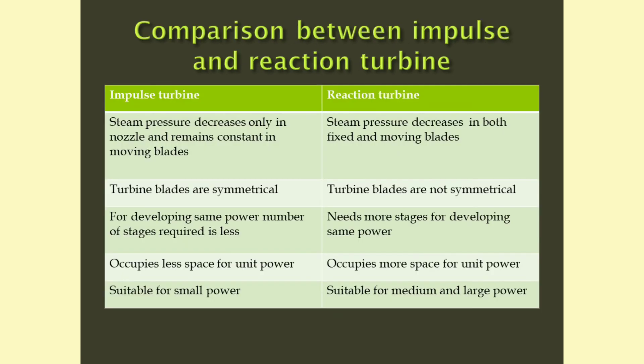We can now compare impulse and reaction turbines. For impulse turbine, steam pressure decreases only in the nozzle and remains constant in moving blades; for reaction turbine, steam pressure decreases both in fixed and moving blades. The turbine blades are symmetrical for impulse turbine and not symmetrical for reaction turbine. For developing the same power, reaction turbine needs more number of stages compared to impulse turbine, and therefore needs more space for unit power, while impulse turbine needs less space. Impulse turbine is suitable for small power applications, and reaction turbine is suitable for medium and large power applications.